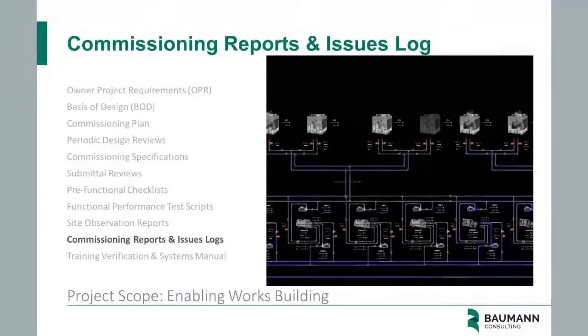This was utilized to verify functionality and performance of the entire chilled water and condenser water systems in real time. So the technician makes a change, we can see temperatures and volumes change, and equipment come online and offline as directed.